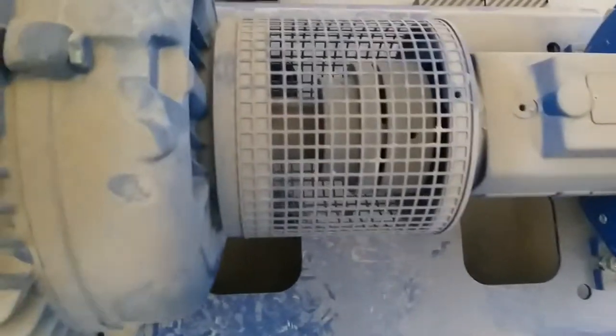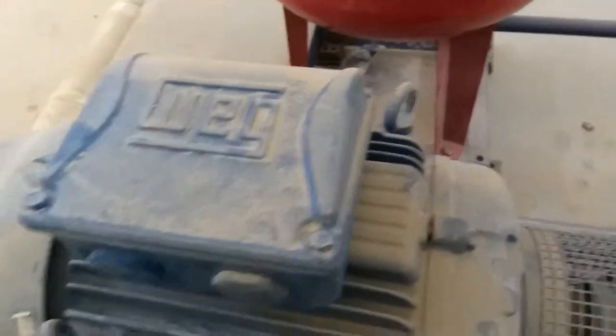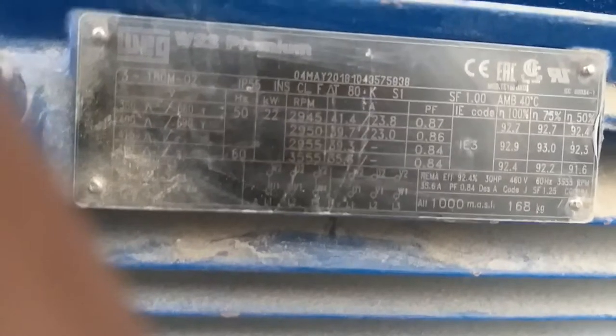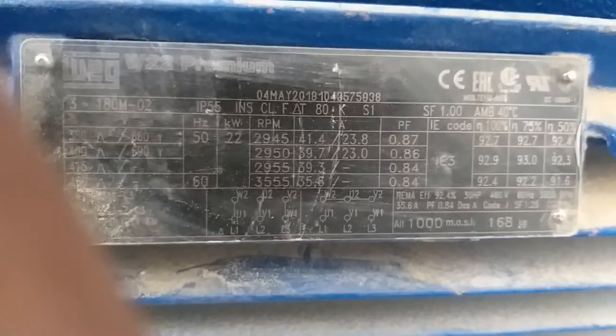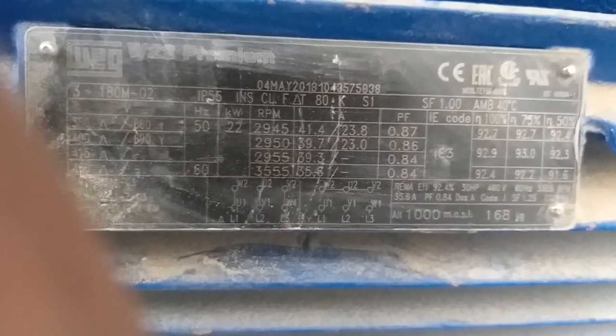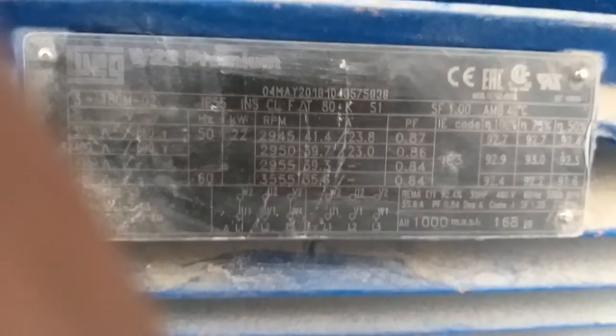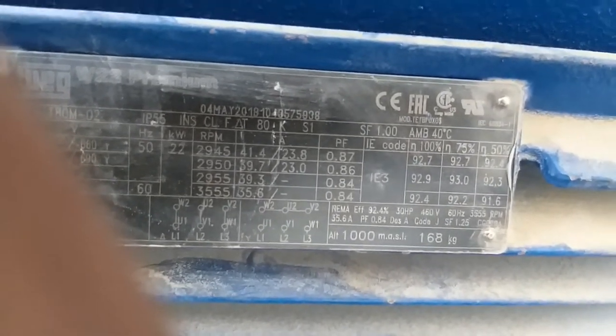We have the shaft here. Let me show you the nameplate of the motor. The winding is IP55 and Class F insulation. The power is 22 kilowatt, and the normal speed of the motor is 2900 RPM. The motor rating is IE3.